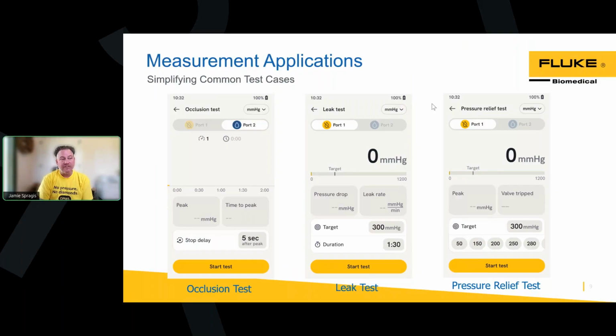Now that valve is supposed to trip prior to that target pressure. What's really cool about the pressure relief test is that if the valve does not trip, the DPM5 will register that. So it'll give you a valve tripped no indication. You could store that measurement and you could run it again. If possibly you have a default pressure relief valve in your monitor, you could test it multiple times.